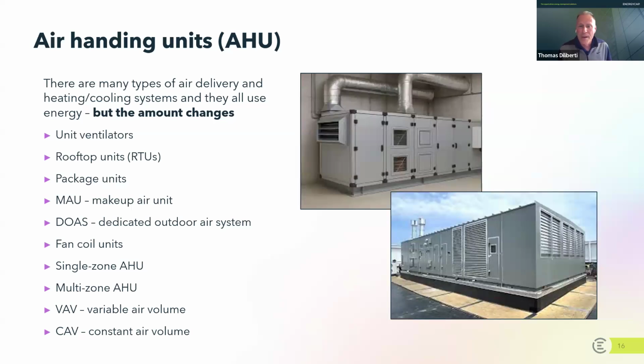Let's run through the list. Unit ventilators are typically small units near an outside wall, many times physically connected to it. A unit ventilator is something we've all probably seen in a classroom—classrooms are notorious for having them. They might be low and flat, or standing vertically within a space. But as I said, they're by an outside wall and allow air to go through the wall into the space as it's heated and cooled.